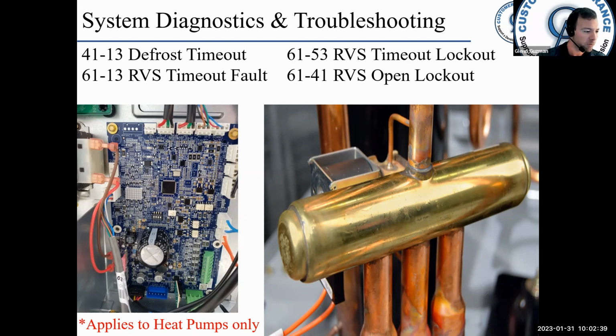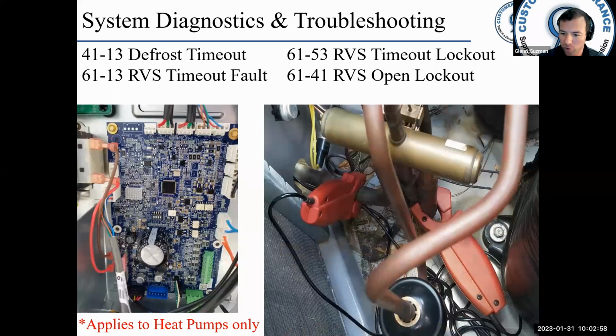When the fault occurs, it may be due to a reversing valve being stuck between heating and cooling positions, or the compressor is not pumping properly. Compare suction and discharge pressure on the app and the UI, and if the pressures are reading correctly, continue troubleshooting the valve. Troubleshooting your reversing valve, right? Checking temperature difference across the valve.